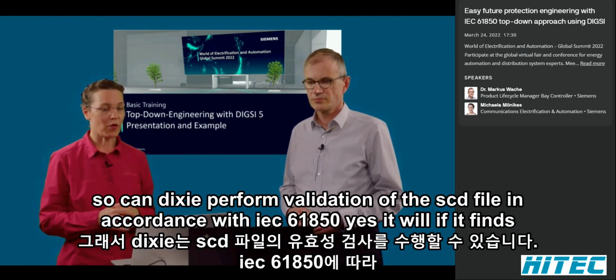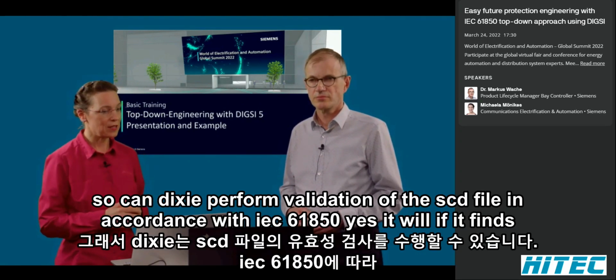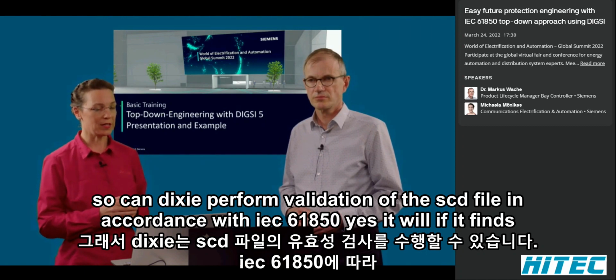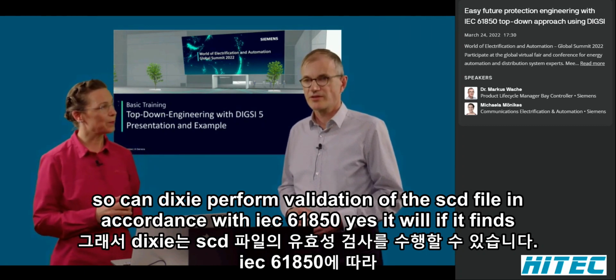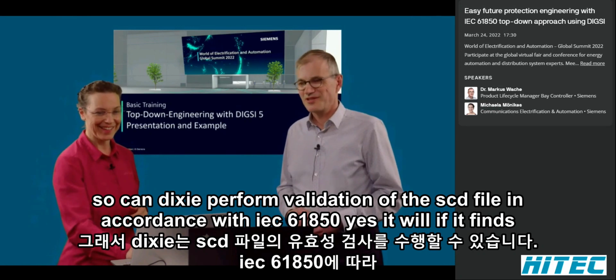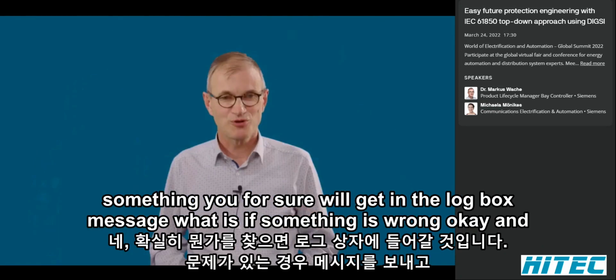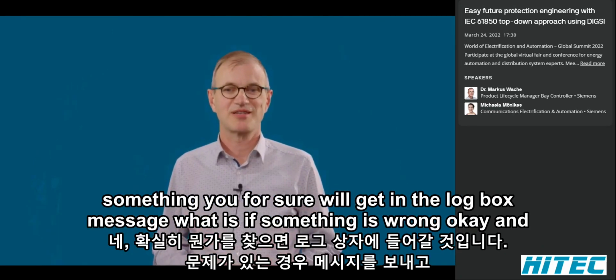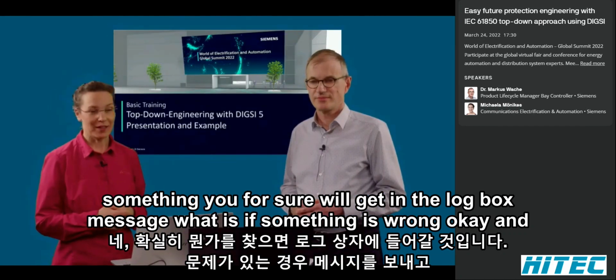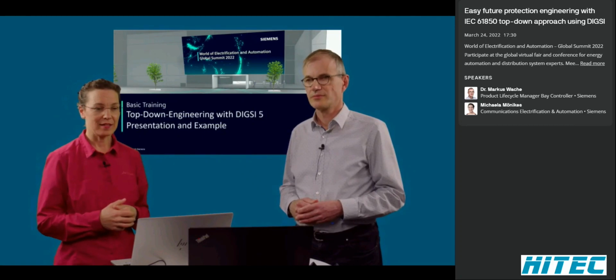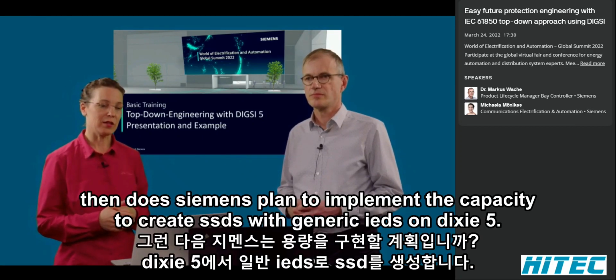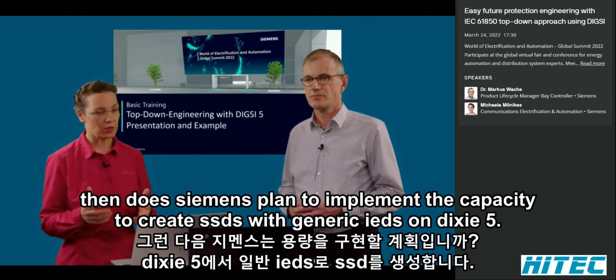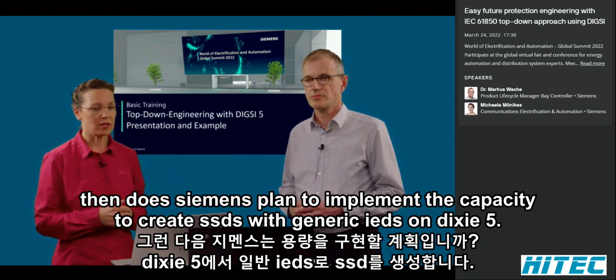So can DIGSI perform validation of the SCD file in accordance with IEC 61850? Yes, it will. If it finds something wrong, you for sure will get a message in the logbox. Okay.